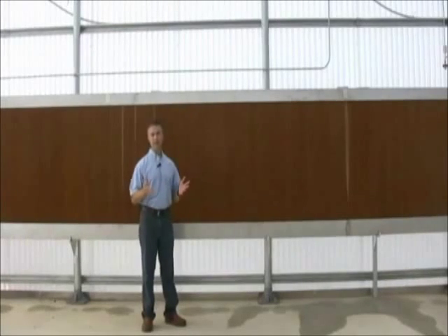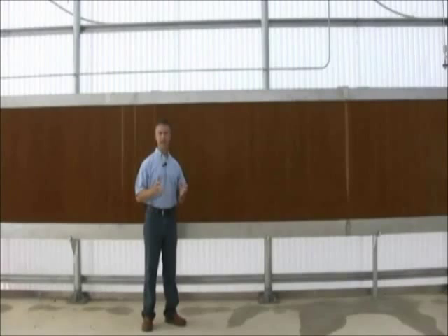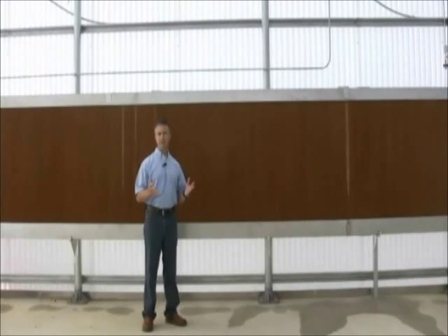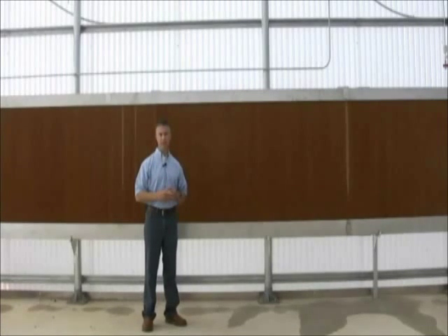So as we've discussed, all of these systems have advantages and disadvantages. Some of the advantages for all mechanical ventilation systems include, first of all, precise control. You can actually control the greenhouse environment more precisely than you can with natural ventilation. Another issue is that you can avoid some of the drafts and potential plant damage along the outside edges of the vents with a natural ventilation system. And finally, these systems are actually less expensive to automate in most cases than a natural ventilation system.